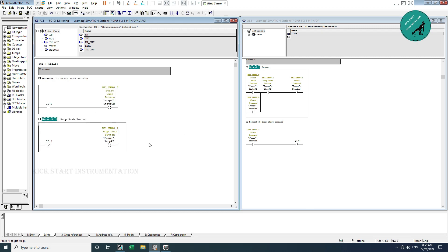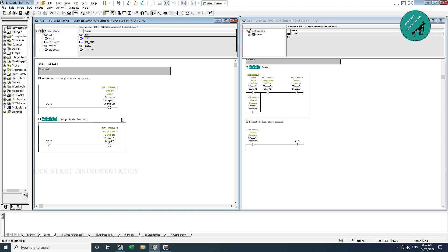I have placed the digital input mirroring in this function. Why? Because we won't have only two digital input signals — we will have many. During diagnostics, if you want to check a particular signal you need not go into OB1, which will contain a lot of logic. If we don't separate things, you have to search everywhere. But if it is in a dedicated function, you can easily identify which address is assigned and diagnose it. That is why we have separate functions for DI mirroring, DO mirroring, and analog input mirroring.